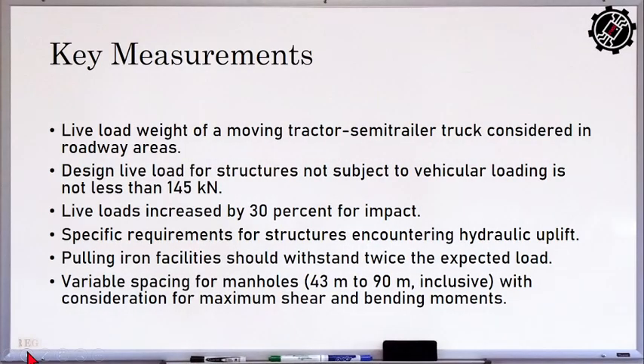Okay, so key measurements natin. So the live load must be equal to a moving tractor or semi-trailer truck for roadway areas. If that is not a heavy traffic roadway, so 145 kilonewton, no, yung minimum. Tapos 30% to increase, and that is now our live load, no? Specific requirement for structures encountering hydraulic uplift, kasama rin yung mga pulling iron facilities, no? Should withstand the expected load. Tapos the variable spacing of manholes is 43 meters to 90 meters inclusive. So the distance between manholes in an underground supply system, a minimum is 43 meters, the maximum is 90 meters.